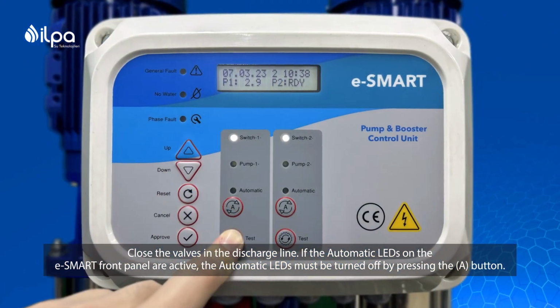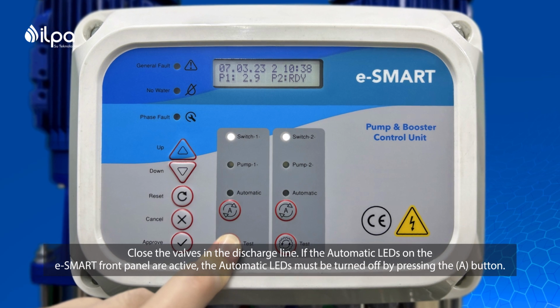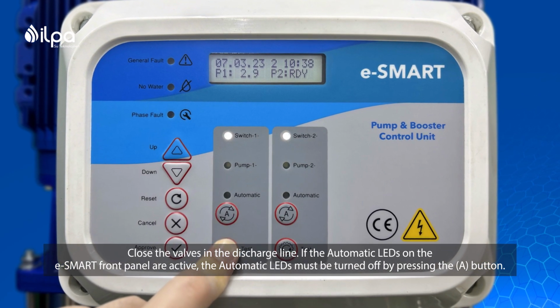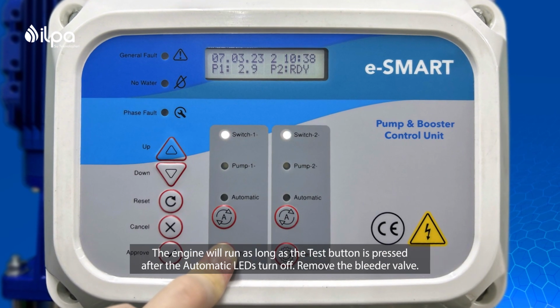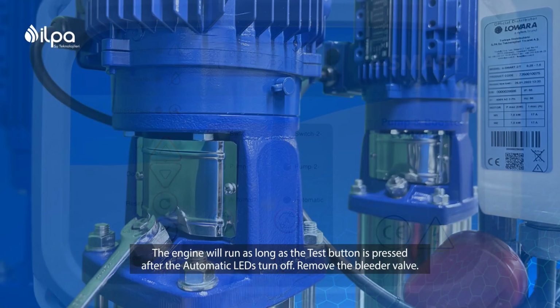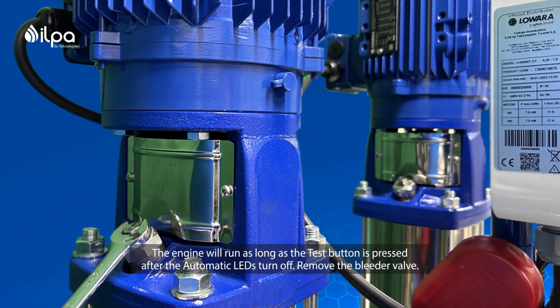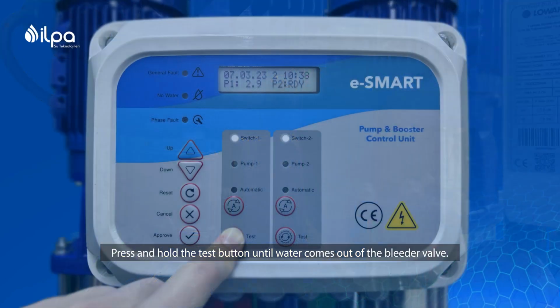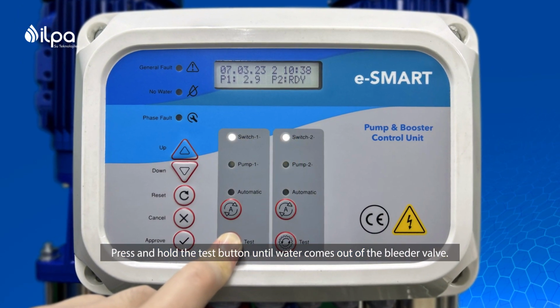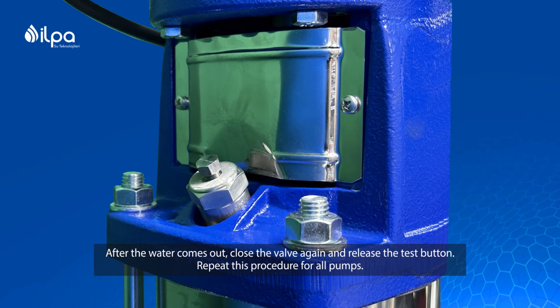If the automatic LEDs on the eSmart front panel are active, the automatic LEDs must be turned off by pressing the button. The engine will run as long as the test button is pressed after the automatic LEDs turn off. Remove the bleeder valve. Press and hold the test button until water comes out of the bleeder valve. After the water comes out, close the valve again and release the test button. Repeat this procedure for all pumps.